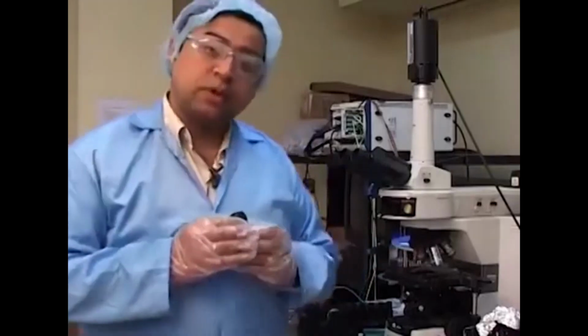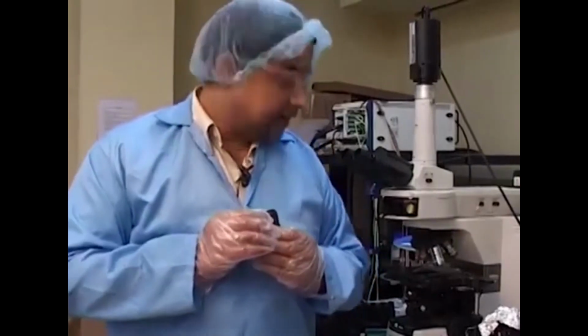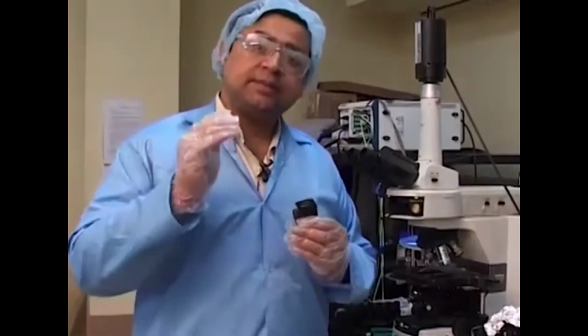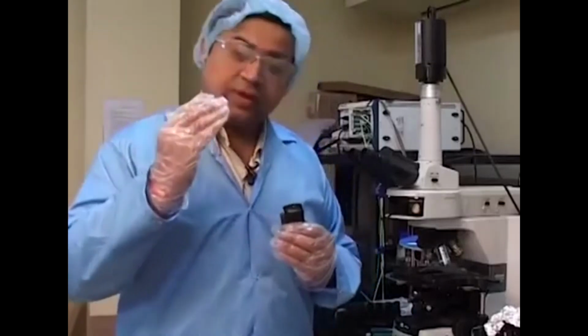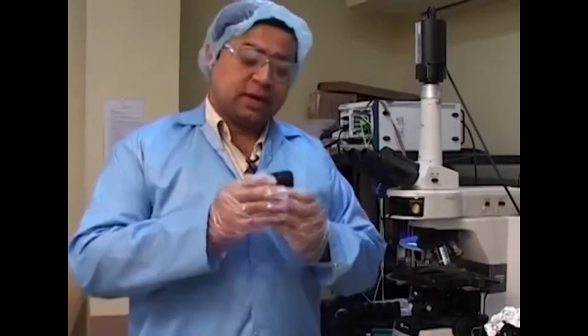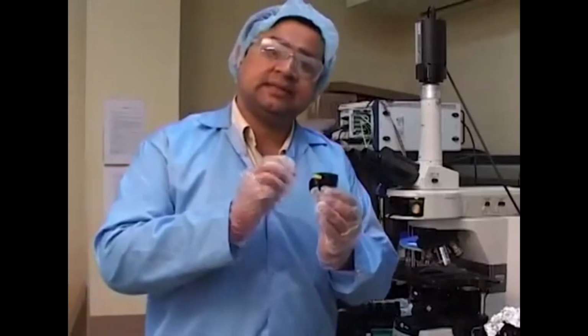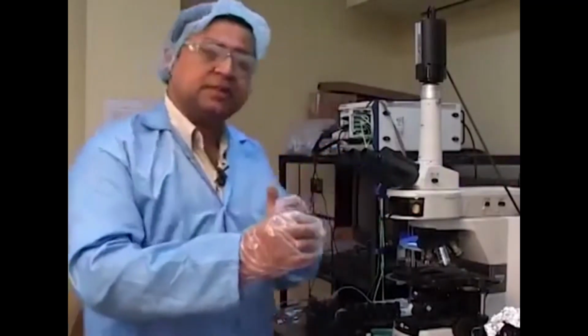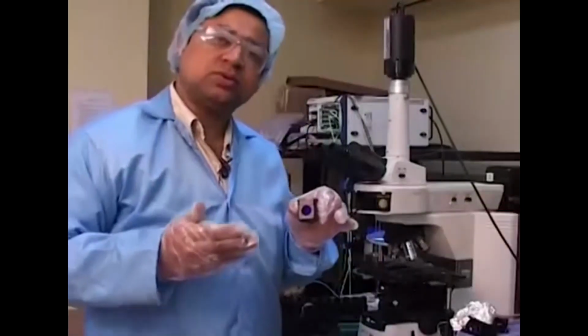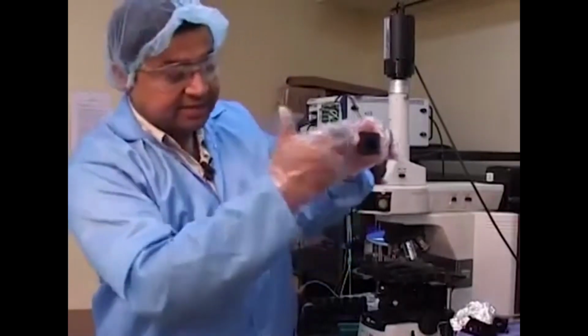As I told you, this microscope also has a capability of doing fluorescence measurements. It is almost always important to be able to excite a certain dye with a certain wavelength of light. Let's say we have a dye which is excitable in the range of 390 nanometers wavelength. So I should have some cutoff mechanism where all the different components of the UV which are coming from the illumination source to this filter should get cut off except the 390 plus minus maybe about 20 nanometers.